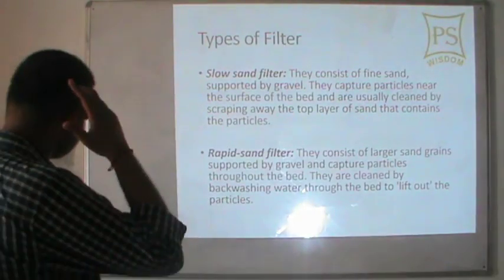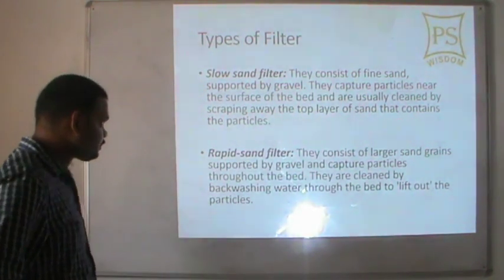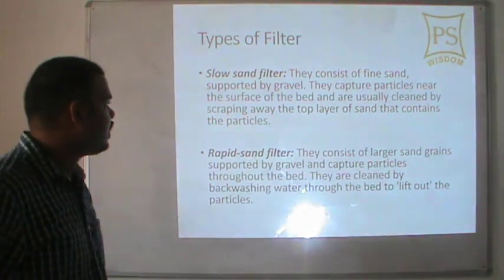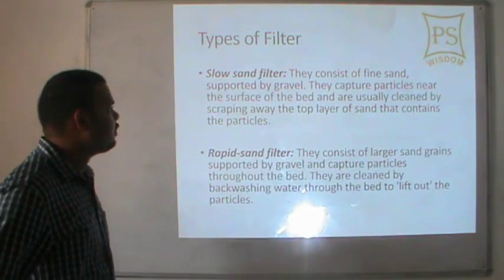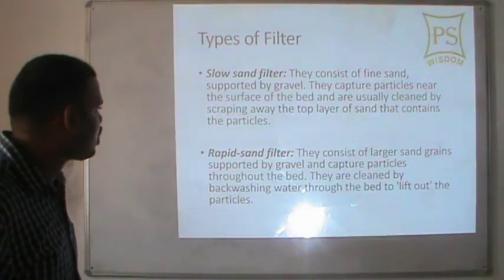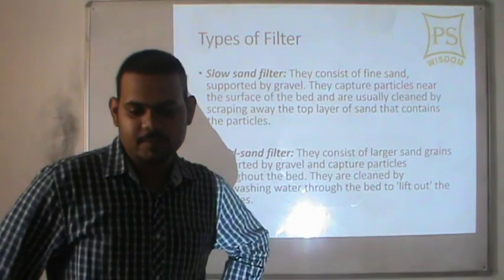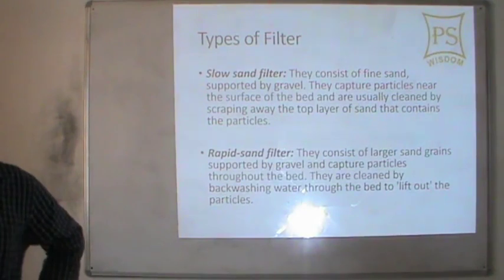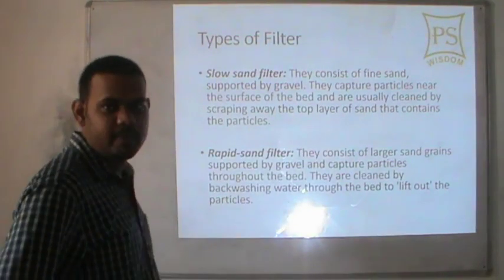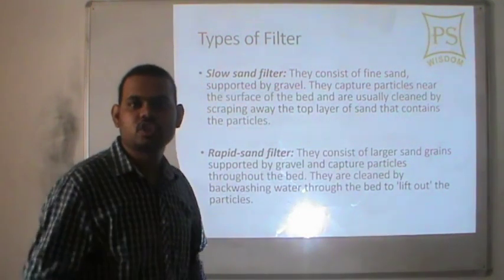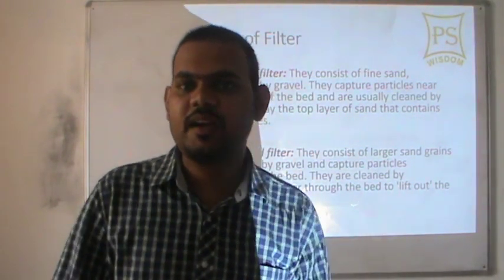There are two types of filters: slow sand filter and rapid sand filter. A slow sand filter consists of fine sand supported by gravel; it captures particles near the surface of the bed and is usually cleaned by scraping away the top layer of sand. A rapid sand filter consists of larger sand grains supported by gravel and captures particles throughout the bed; it is cleaned by backwashing water through the bed to lift out the particles.